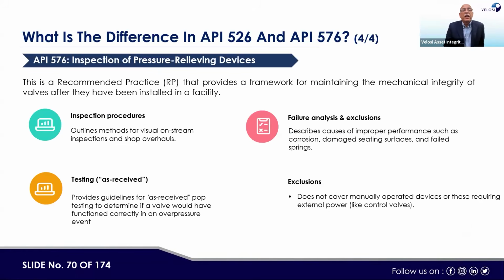Whereas in API 576, inspection procedures are important, testing procedures are prepared, guidance is provided, then failure analysis and exclusions: how a valve can fail, what the causes of failure are, and how those failures could be minimized, what kind of inspection regime there should be, what the PSV testing interval should be, as-received pop testing procedures, and so on. All those areas are covered under this standard.